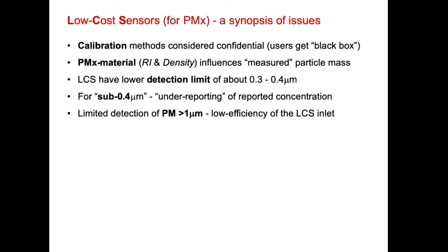Remember the summary given by Professor Furucci in a previous talk. What was very interesting for me to see from the data obtained by NanoNet, which is a wonderful organization by the way, is that he indicated that the fossil fuel burning particles of interest or importance are larger than 0.5 micrometer. That's something where we could start thinking low-cost sensors may be good as a complementing instrument there. So if we don't measure particles smaller than 0.4, we are many times underreporting the concentration, especially if we have single particle counting.